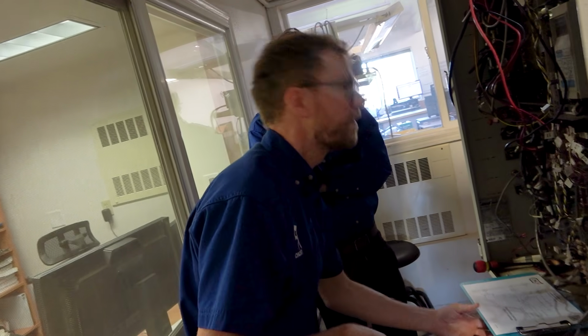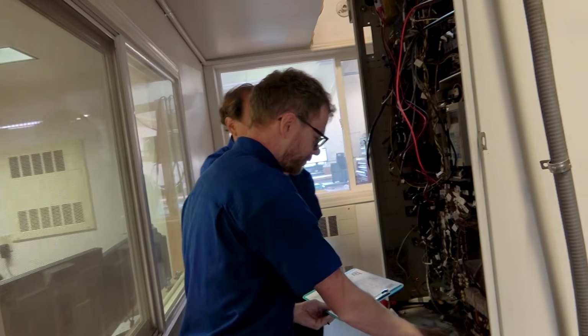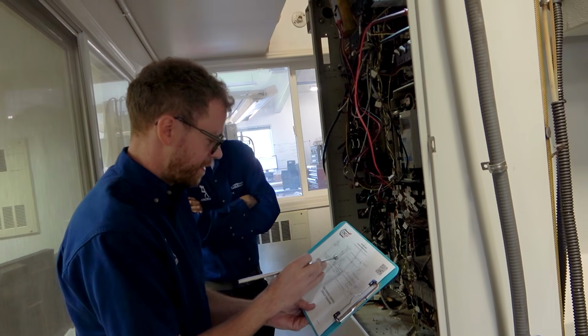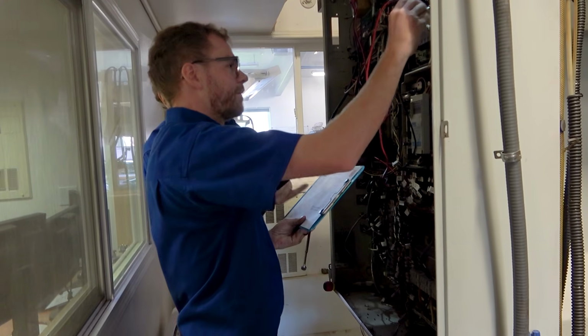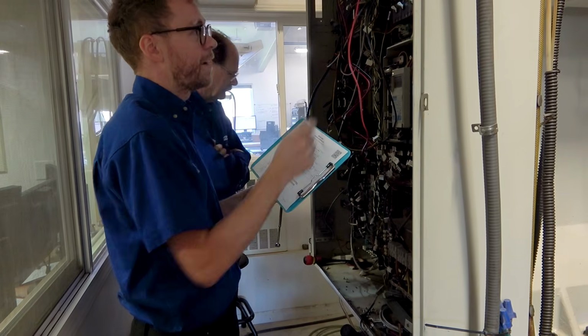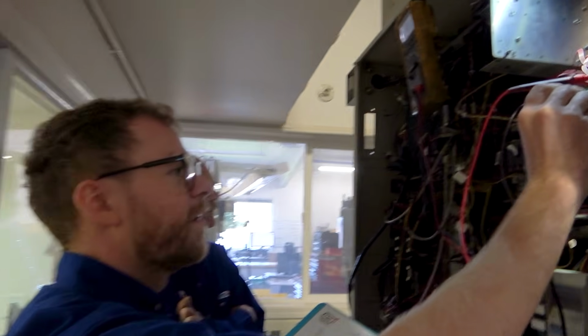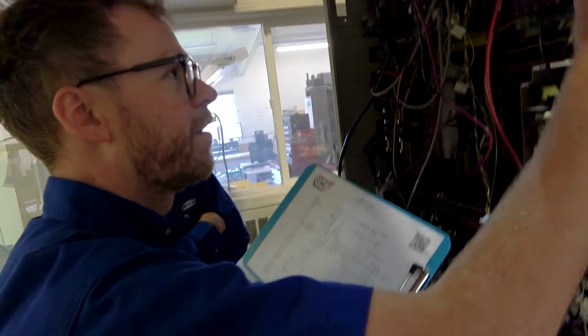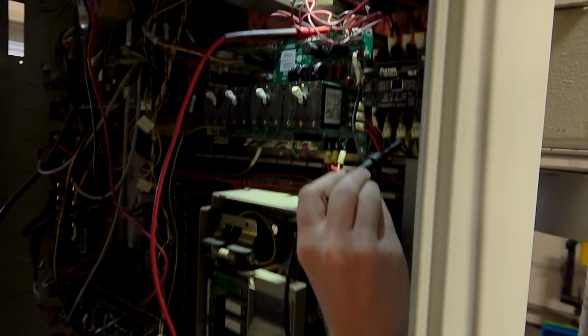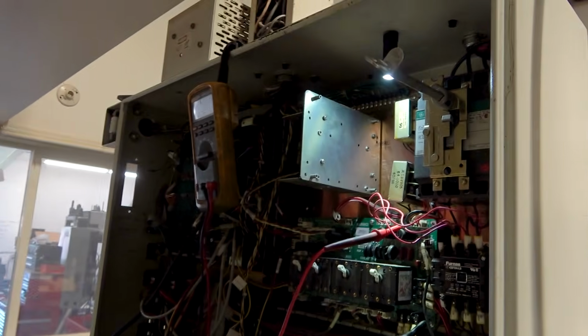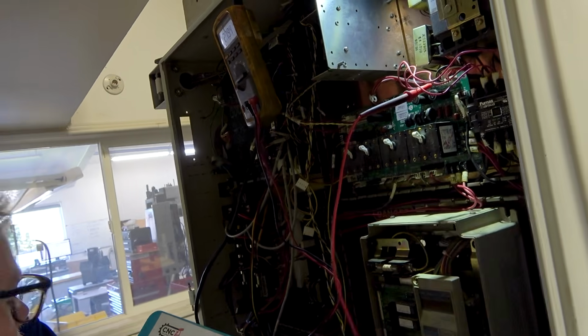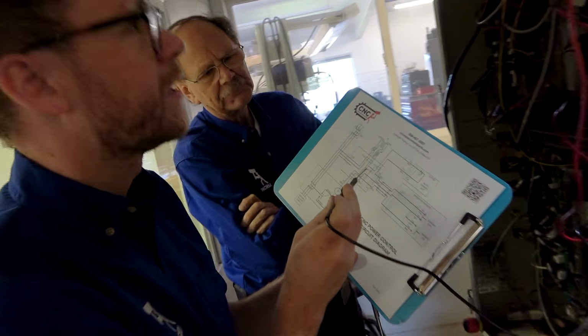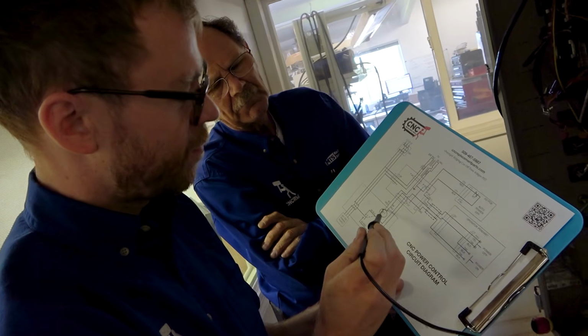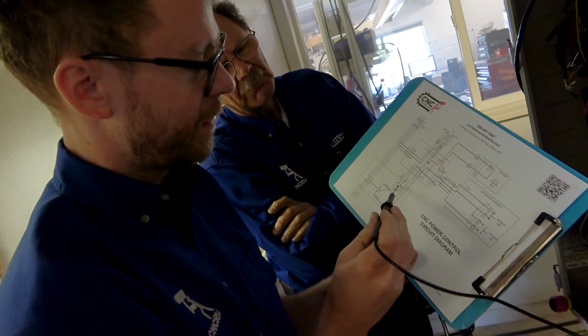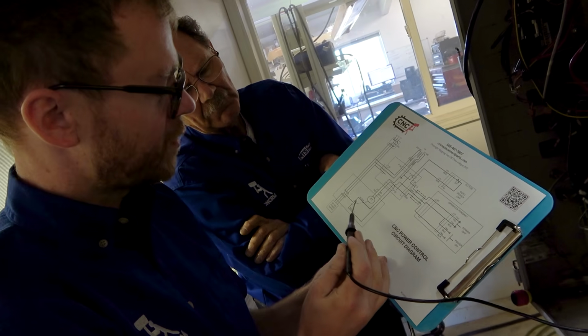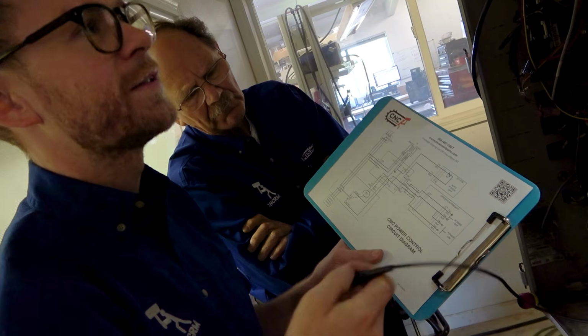Let's keep going. Okay, 28 volts right here going to this coil - this could be the next problem if the machine doesn't turn on. If I'm measuring here going to the coil, that's black. If I measure down here, I've got 28 volts. On the other side, 28 volts. So with my meter grounded on this red wire, I've got 24 volts here, 28 volts here, 28 volts here. That means I should have 28 volts on 69, the black wire going to the contact.